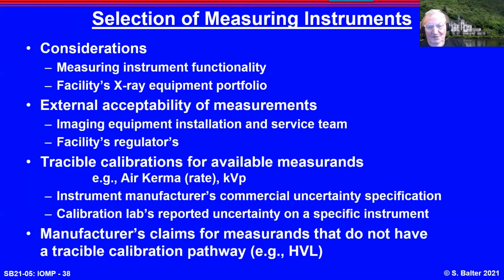Look at the traceable calibrations, instrument manufacturers' specifications, calibration lab. A particular issue is many instruments now provide a half value layer reading. There are no international standards. There's no traceable calibration for indirect half value layer. Look at this carefully.